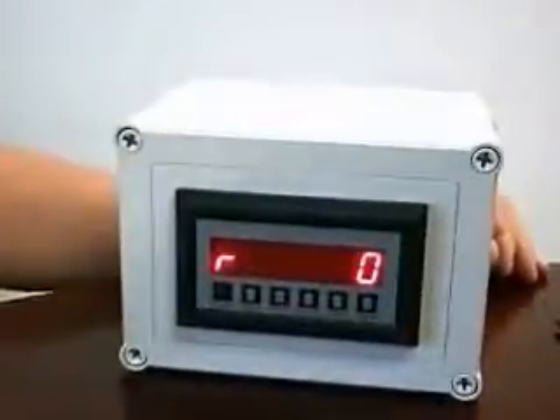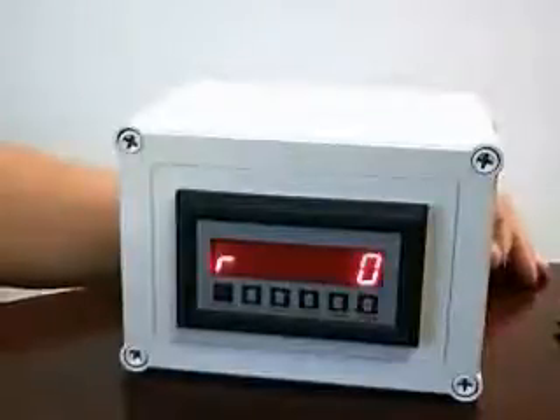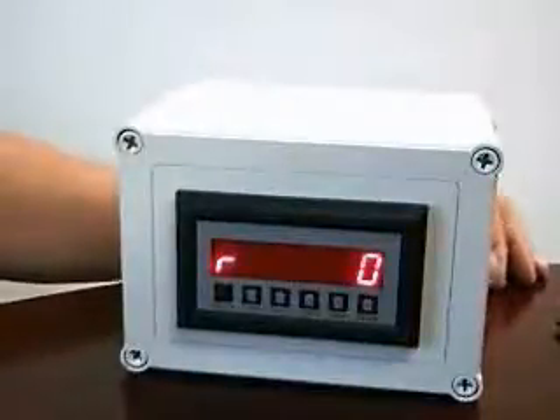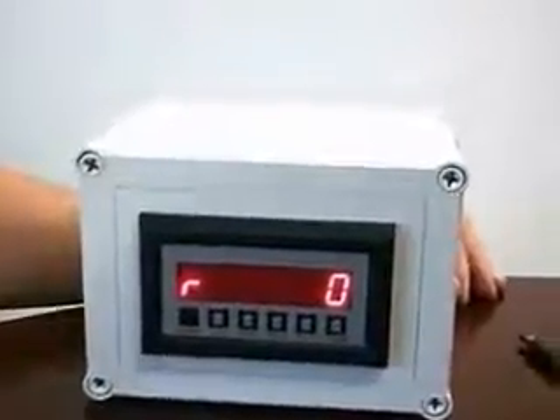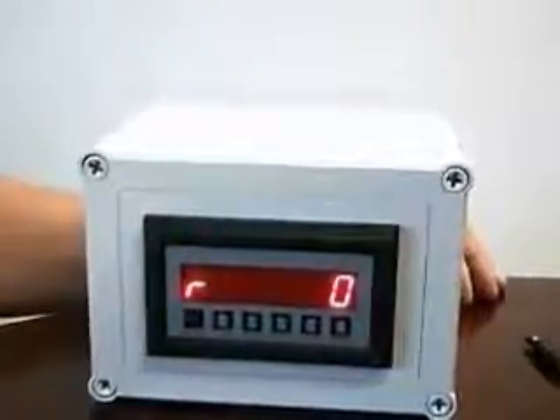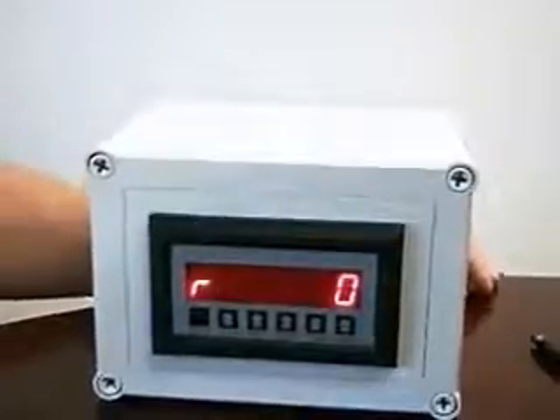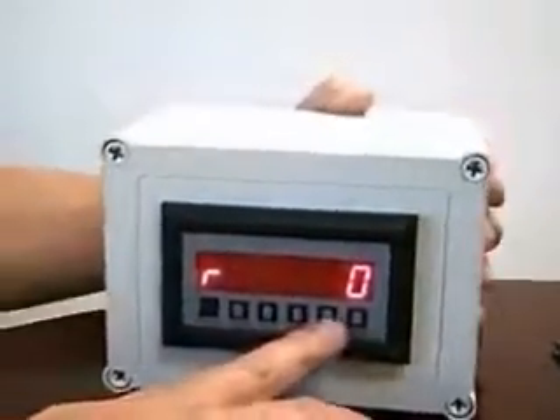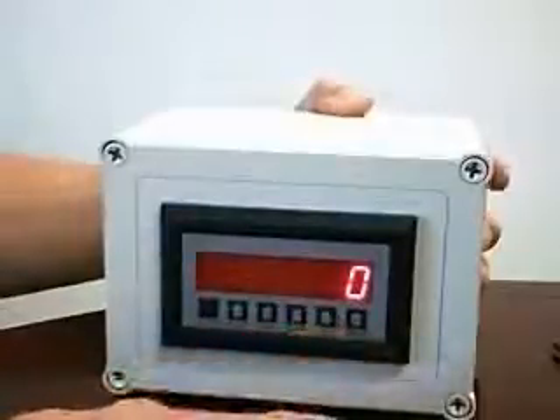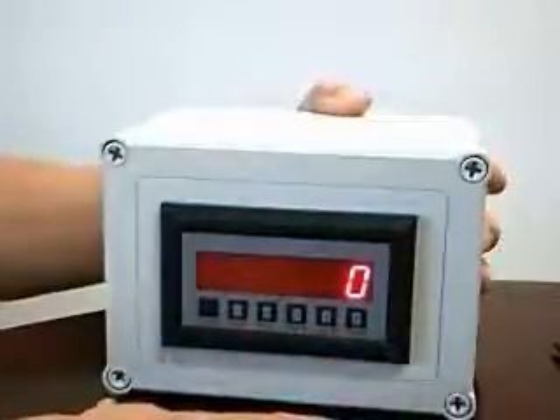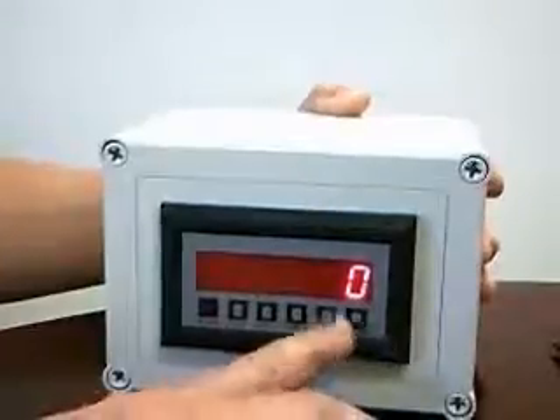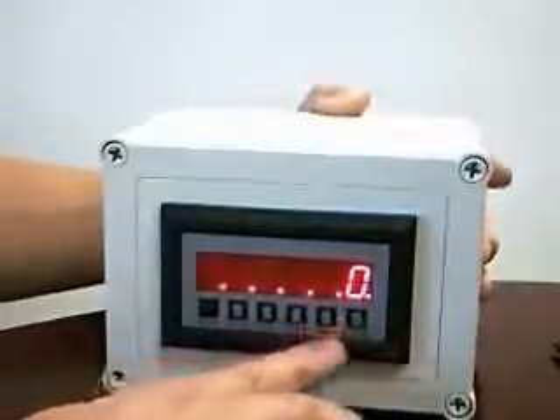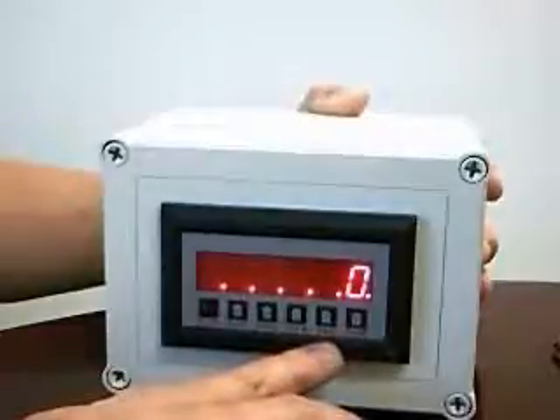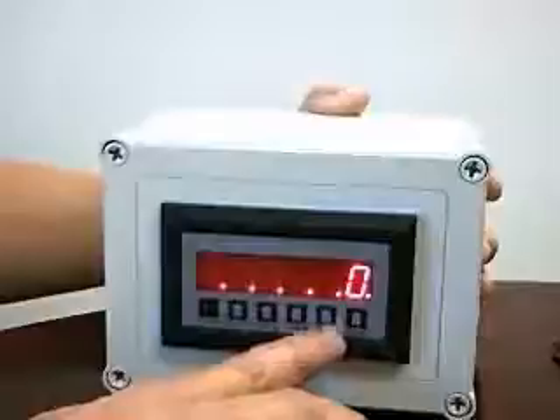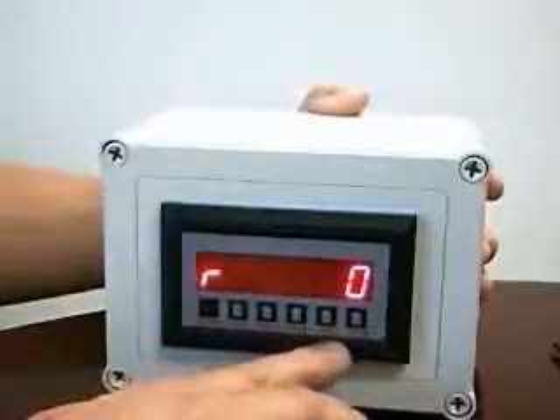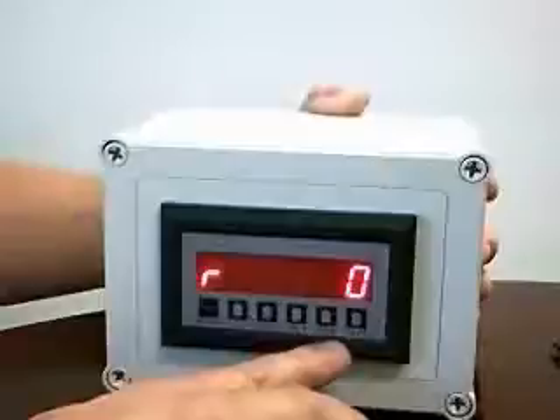You'll notice initially that the display has an R in the far left-hand side as well as a numerical value. This is showing you the flow rate. To view the other indications on this device, you press the view button. The first item is showing you the total on the A channel. The second, where all the decimal points are lit, is showing you the total on the B channel. Pressing the view button again returns the display to showing you the rate.